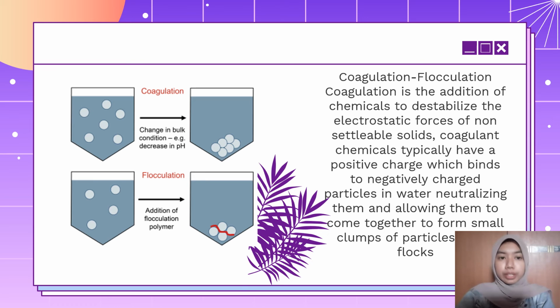And water temperature, for example, colder water usually slows coagulation and flocculation reactions, which may require more time to achieve optimal floc formation. Extreme values of pH, high or low, will also interfere with the process. Coagulant effectiveness is highly dependent on pH. Turbidity is also important. The lower the turbidity, the more difficult it is to form proper floc.